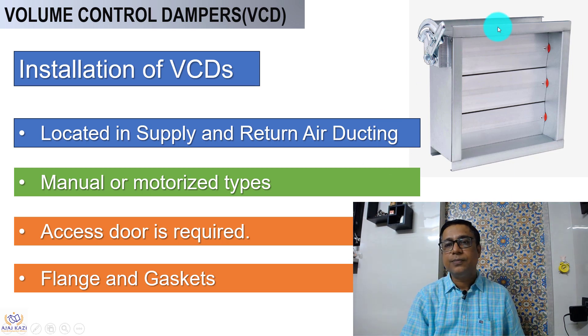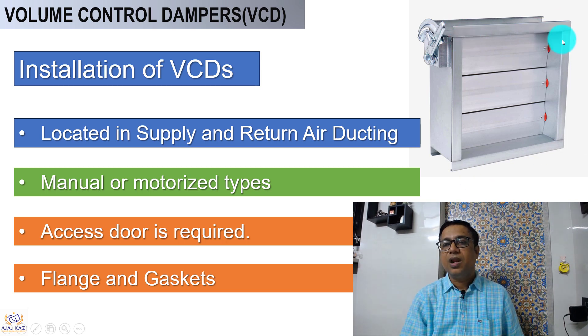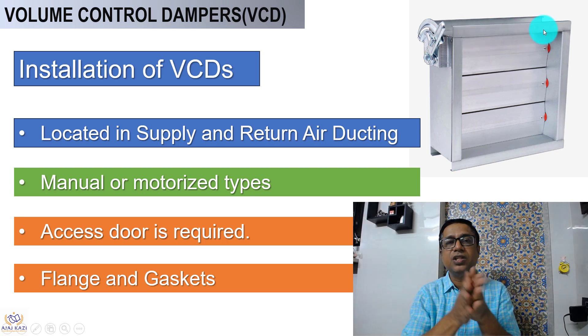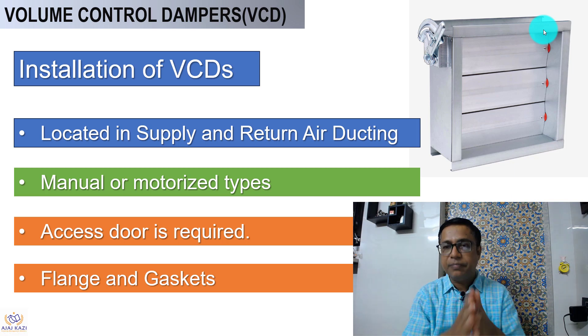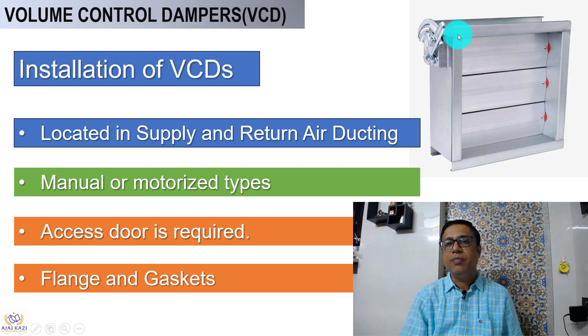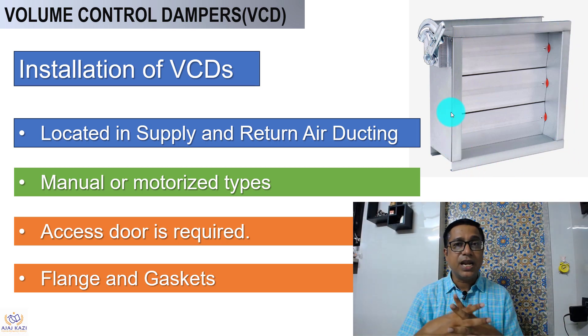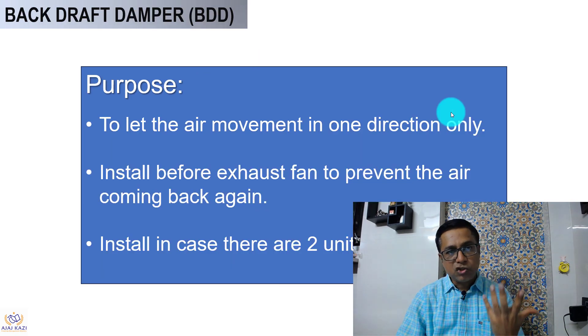Just to explain: this is a flange made of duct, and it can connect to a 4-bolt duct system. There will be a gasket so when the duct flange comes in, there is no leakage. There will be clamps to hold this together with the gasket in between. You can also put holes for nut-and-bolt connection with the connecting duct. This is the installation for VCDs.